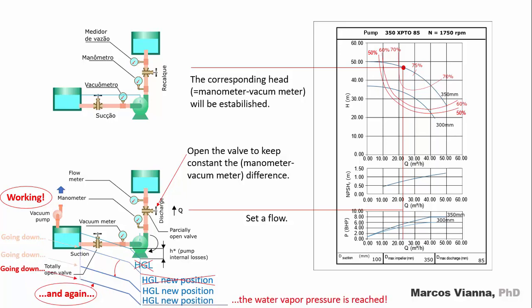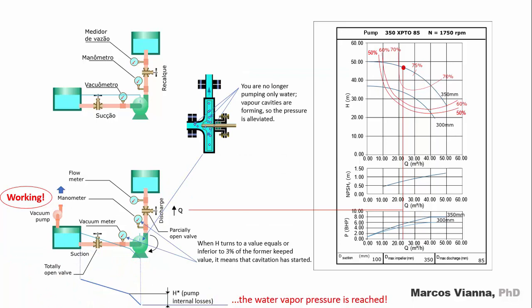Let's do the same again until the water vapor pressure is reached. How do I know it's been reached? It's simple. When the manometer vacuum meter difference turns to a value which is equal or inferior to 3% of the value that we were keeping, it means that cavitation has started.